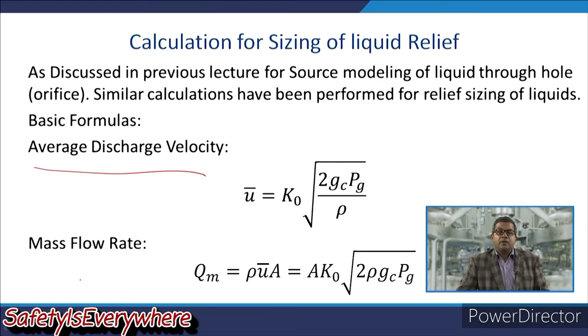So, the discharge area you can calculate by calculating the average velocity, it is a normal fluid dynamics phenomenon, the average velocity, and substituting it into the mass flow rate equation. Now, this k naught is the discharge coefficient for the preliminary sizing. This can be assumed to be 0.65. So, adjustment for the back pressure and velocity correction can be done by replacing k naught with k, where k is equal to k naught kw kv, all in multiplication, where kw is the correction factor for back pressure and kv is the correction factor for viscosity.